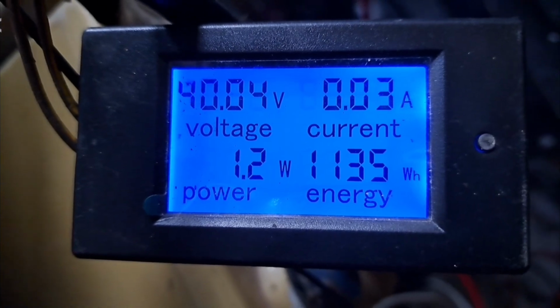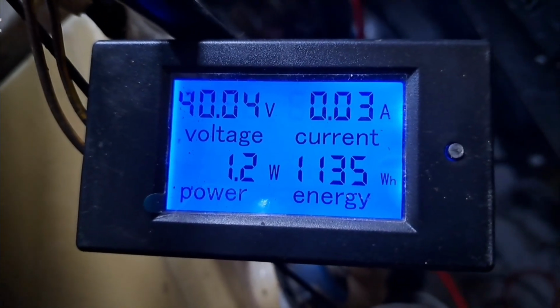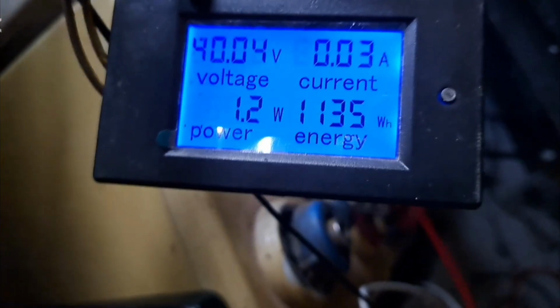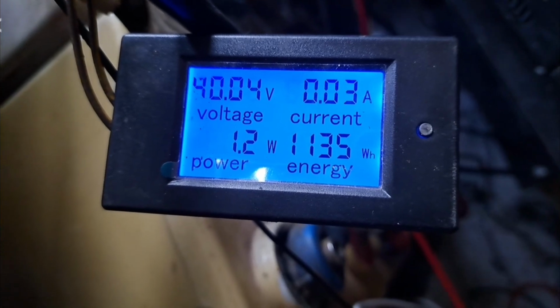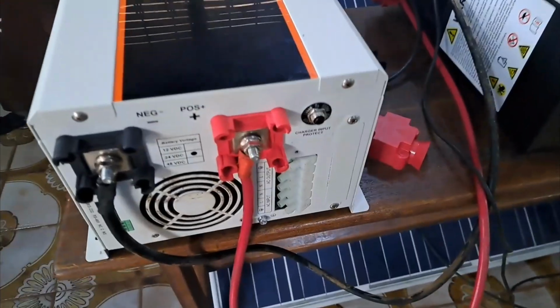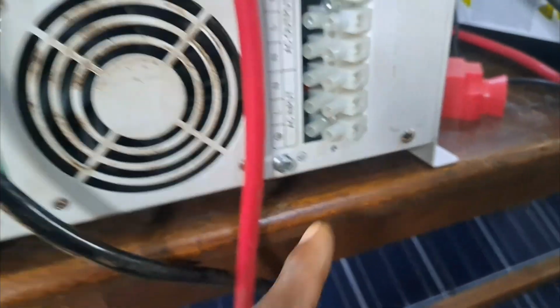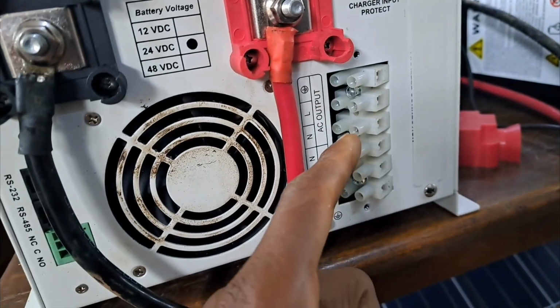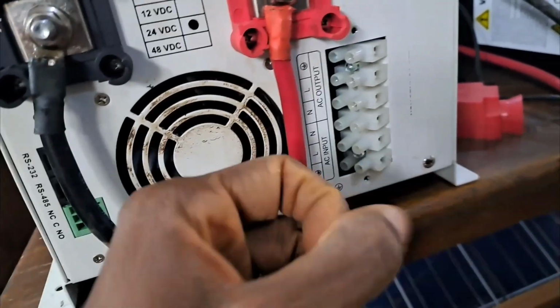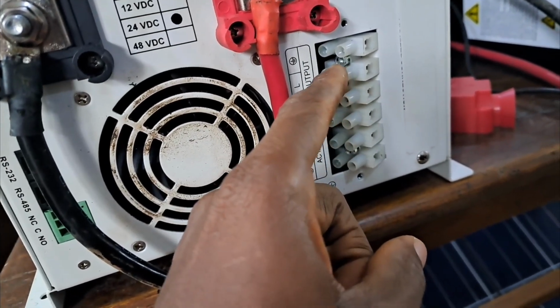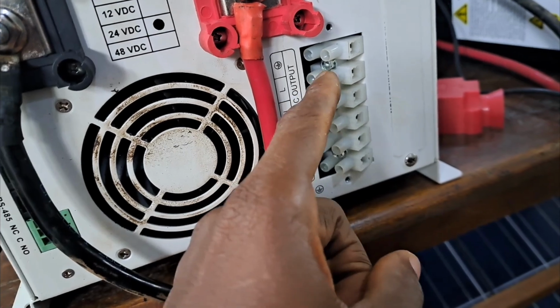So what does that tell you? If you have a lithium iron phosphate battery, say a 5 kilowatt hour battery, and you connect a 10 kVA inverter to it, remember, the bigger the inverter, the more it consumes. You'll find that within 24 hours, just having the inverter on without connecting any load will run the battery down.